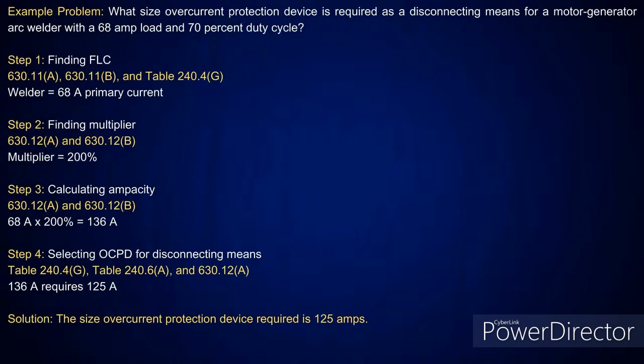So I've got a 68 amp load, and it has a 70% duty cycle. If I was sizing the conductor, I would definitely use that 70% to size my conductor. But what we're pointing out here is that, sizing the overcurrent device, I'm going to take it at 200%. If I take 68 amps at 200%, it says rated or set not more than 200%. That means I can't exceed it. So the next size below that 136 amps is a 125 amp overcurrent device.